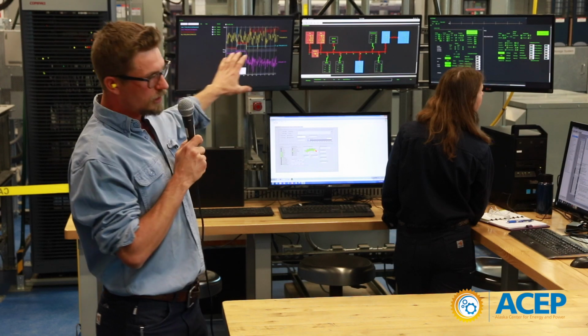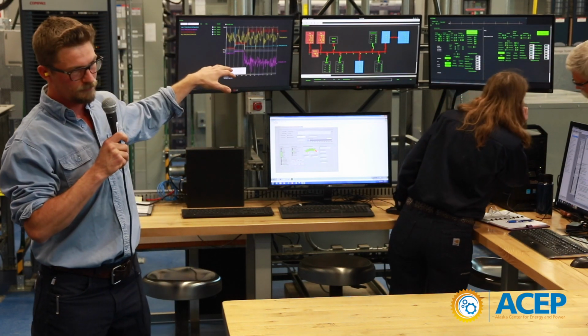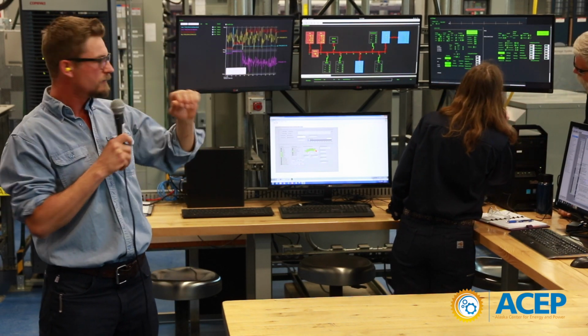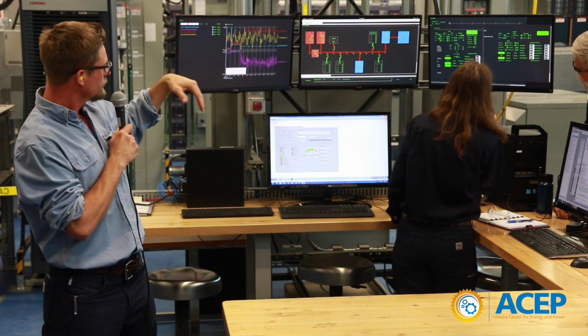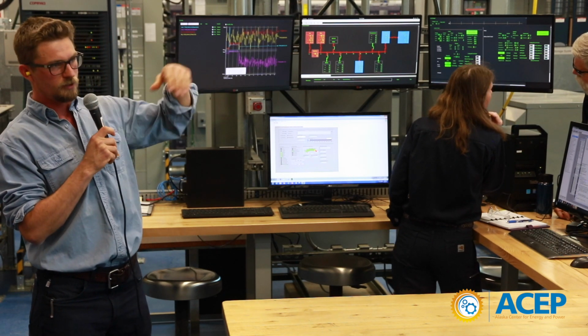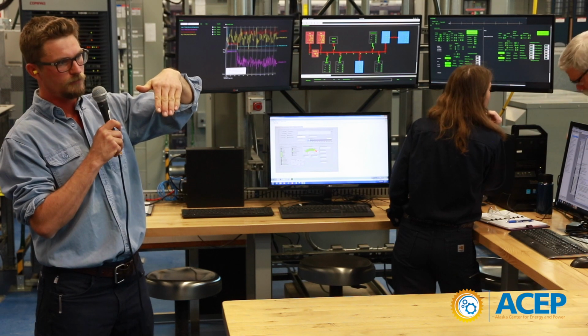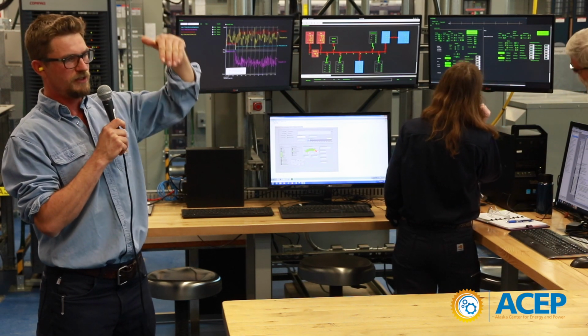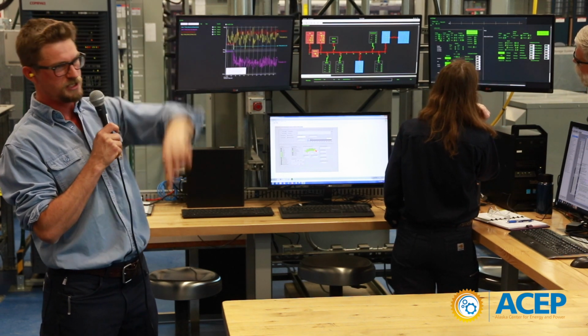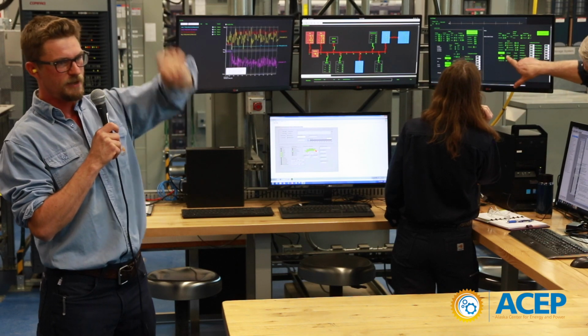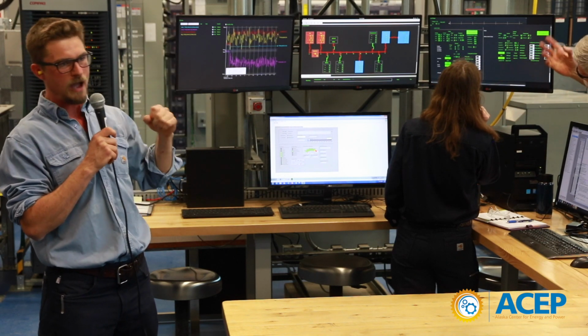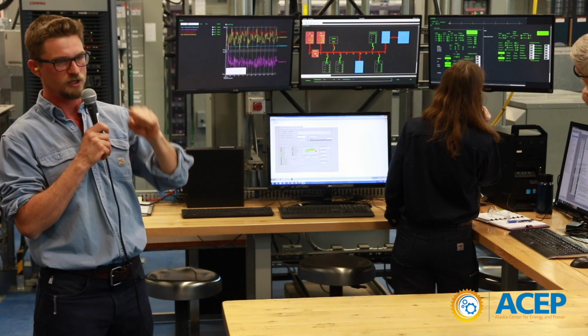Basically, we're running our inverter in droop, which means we try to get it close to zero at 60 hertz, and then it will respond to changes in frequency. When there's a spike in frequency, it absorbs power, and when there's a drop in frequency, it pulls power out.